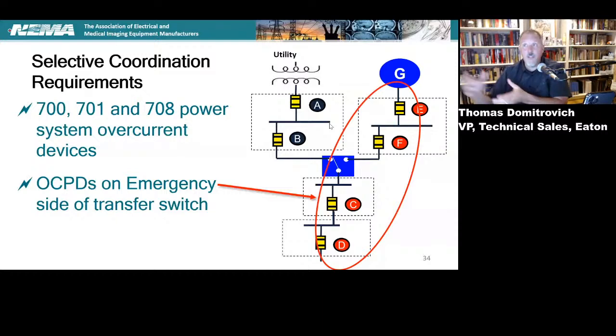I think the drive is in that region, but what it really does is it puts the onus on the PE to be making a decision on how they want the performance of this system to function. And some would argue that is the job of the PE, that they need to weigh the cost with reliability, with arc flash, and maybe they do redundant, dual redundant, triple redundant systems in lieu of coordination. It's all up to the engineer. But that's the difference between the 0.1 seconds and the selective coordination.